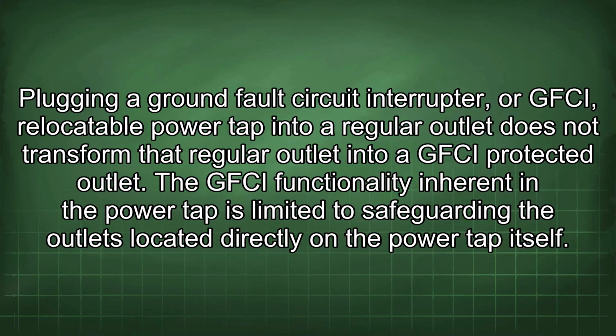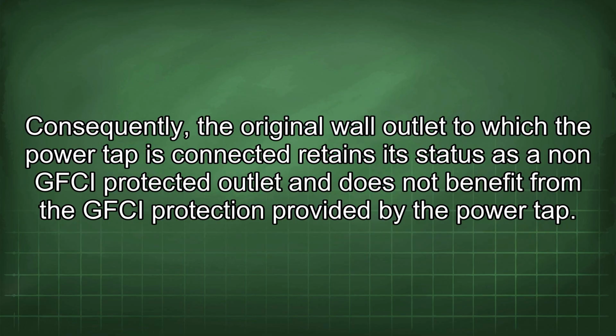Plugging a ground fault circuit interrupter, or GFCI, relocatable power tap into a regular outlet does not transform that regular outlet into a GFCI protected outlet. The GFCI functionality inherent in the power tap is limited to safeguarding the outlets located directly on the power tap itself. Consequently, the original wall outlet to which the power tap is connected retains its status as a non-GFCI protected outlet and does not benefit from the GFCI protection provided by the power tap.